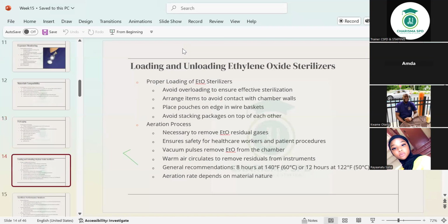Okay. So loading and unloading ethylene oxide sterilizers is nothing new. All you have to have in your head is that I have to load it properly and I have to unload it properly. The different thing that will come up here is the aeration process, where we leave the load exposed to air, warm air circulating, to remove the residuals. That's going to be the only difference. Proper loading: avoid overloading to ensure effective sterilization. You know that already. Arrange items to avoid contact with chamber walls.